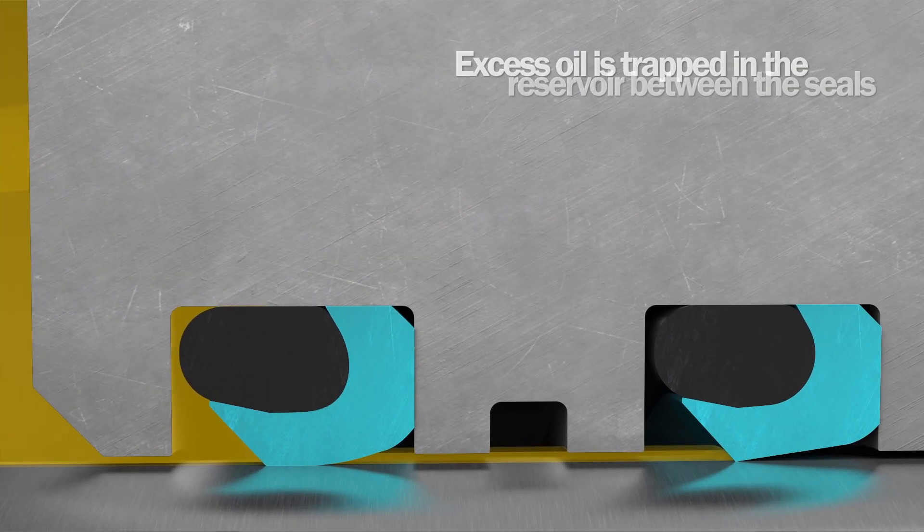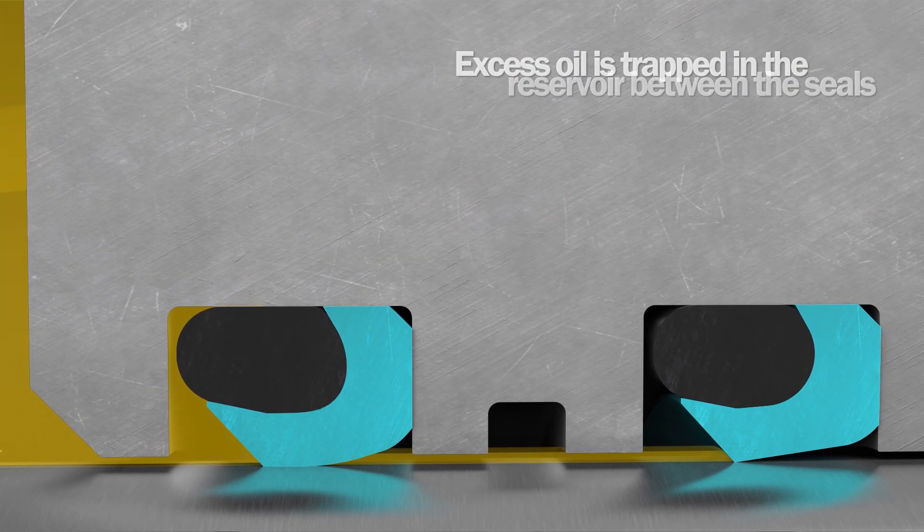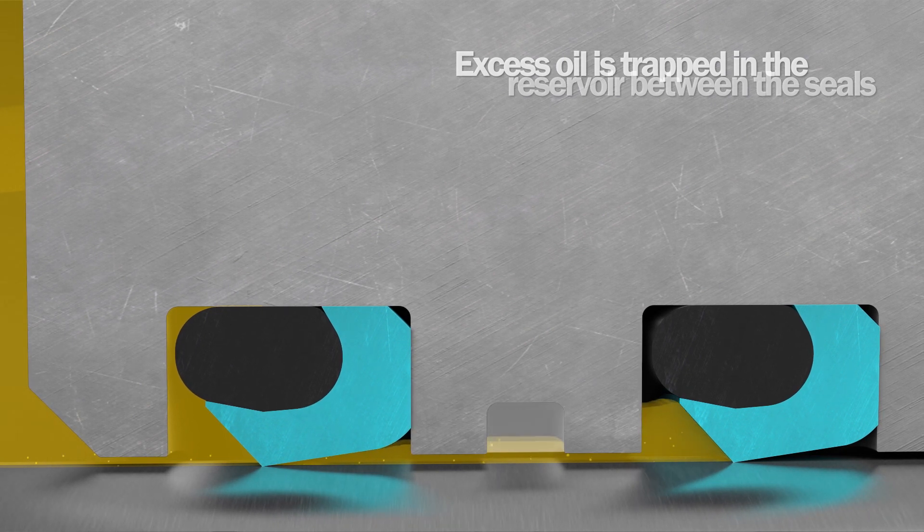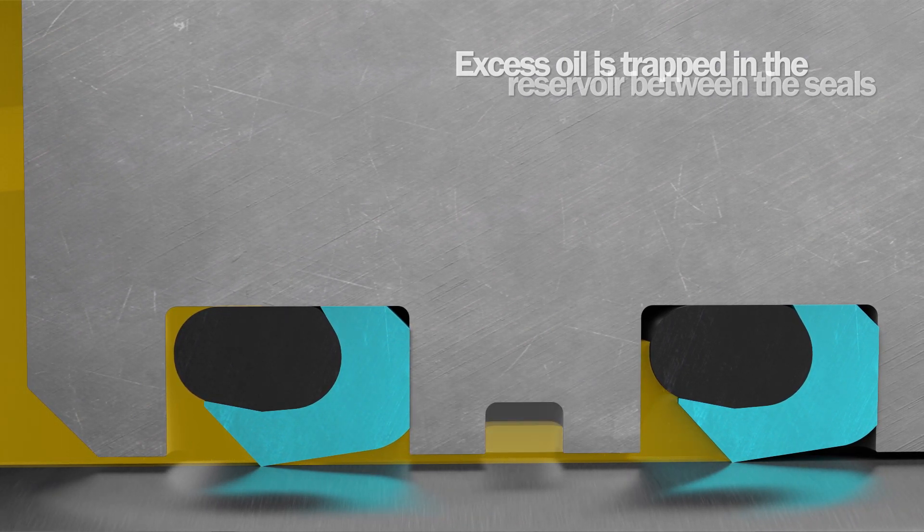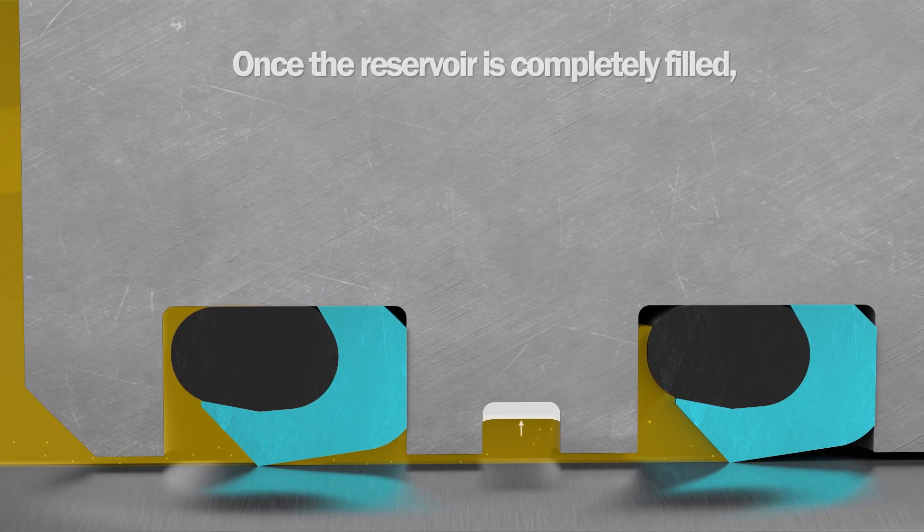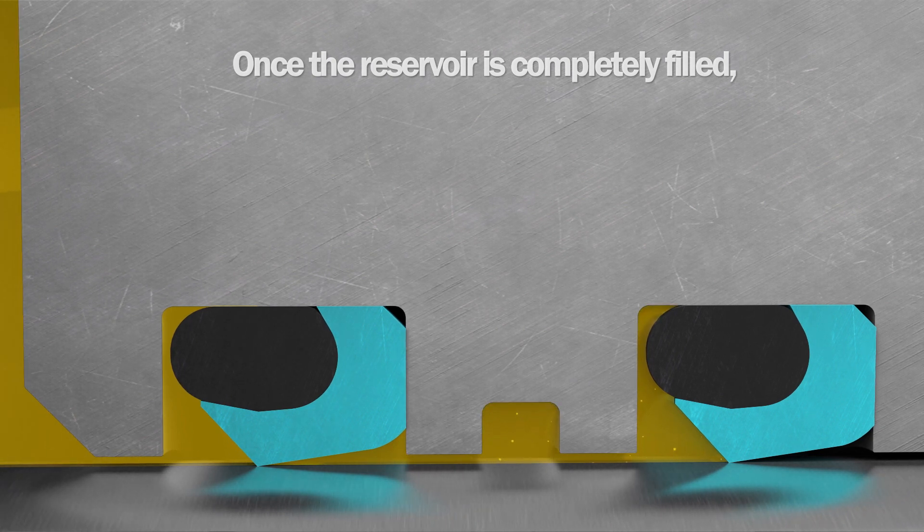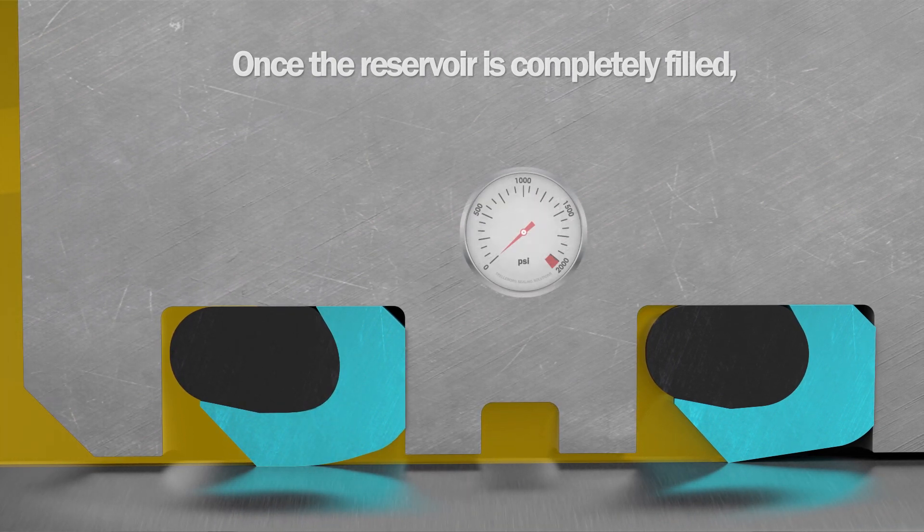Any additional oil is trapped in a reservoir between the seals. With the reservoir filled, pressure between the primary and secondary seals increases.